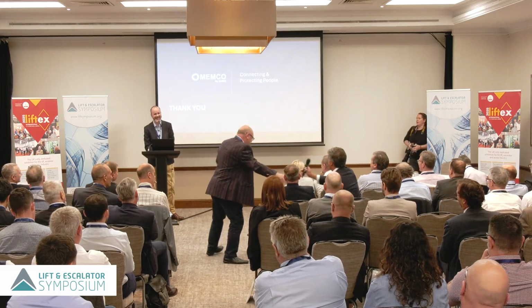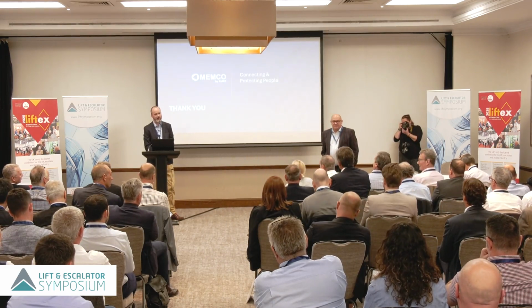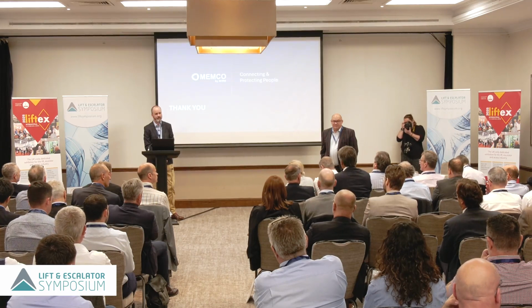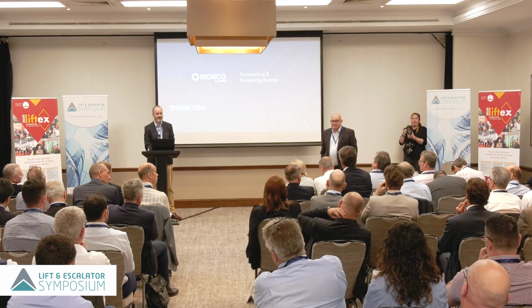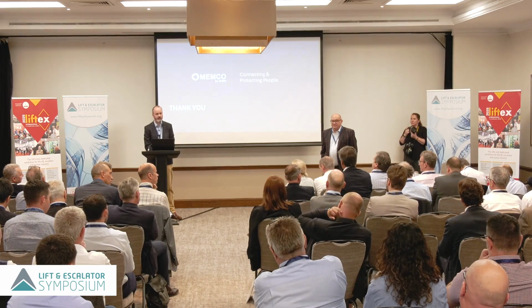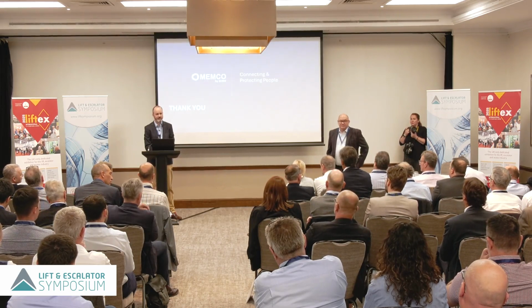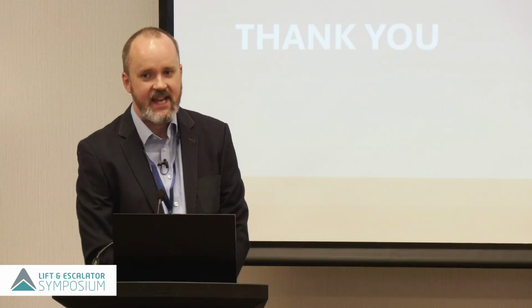Adam. Hi, Matt. Adam Scott from Swaco. Great presentation, thank you. You mentioned that where you moved to GSM, everything comes under the control of the lift contractor. We've got projects in central London where the lift contractor has installed a GSM system and is unable to hand the lifts over because the signal is not strong enough, because of the surrounding buildings, the installed environment and the mobile reception network. We're now in an impasse situation where they're saying we've got a big issue here, and I'm just keen on your thoughts on that.